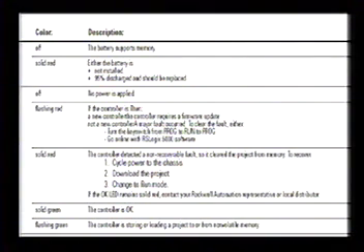If this OK light's solid red and stays red, and you've tried everything, you need to get that processor swapped out. Actually, they'll send you a new memory module, and you install it, and then you put the old memory module back in a bag and ship it back to them. And I think the service is actually free. I know certainly if you have a support contract like we do.